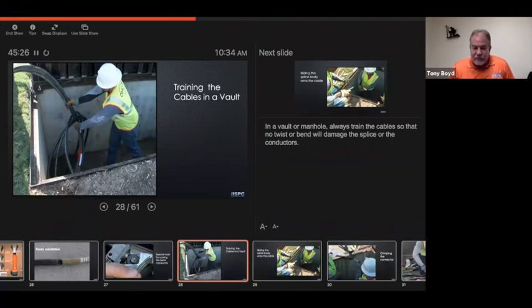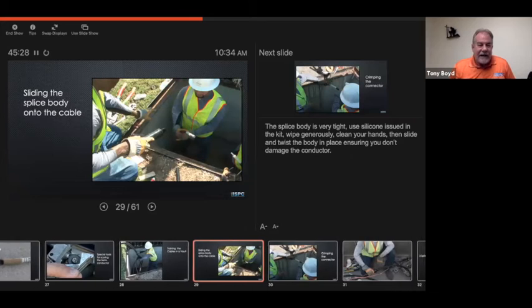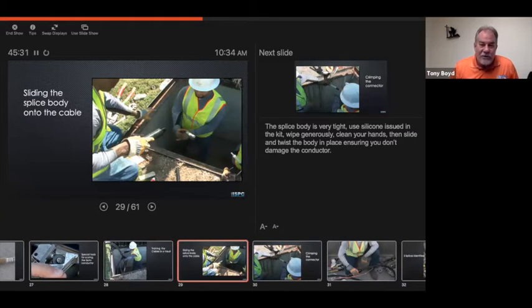All right, sliding the splice body onto the cable. This is usually the toughest part. You see the guy is actually holding the cable itself. Before this picture was taken, they put silicone on the cable. At the bottom right of this picture, you see the other end of the cable that's going to come on and be spliced. And like I said, this company uses those cold shrinks, so they went in and put the cold shrinks on before this operation.